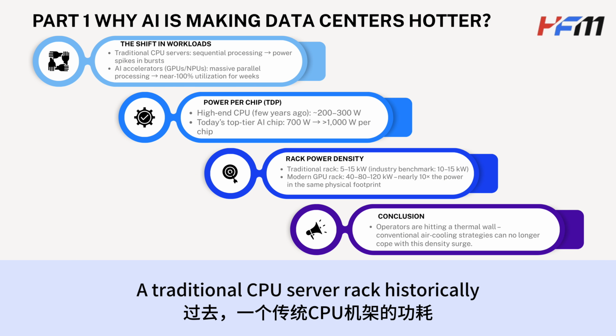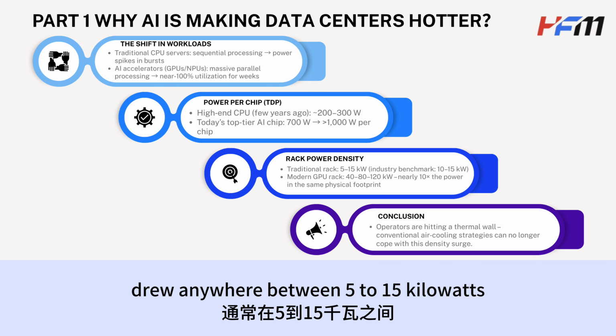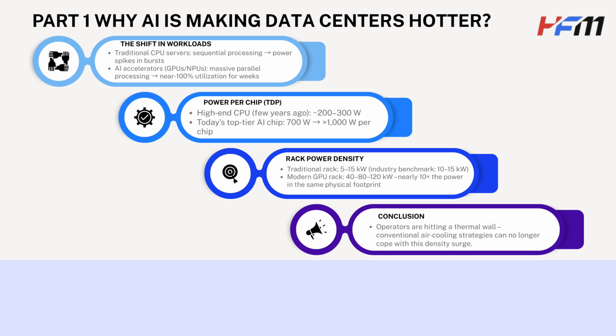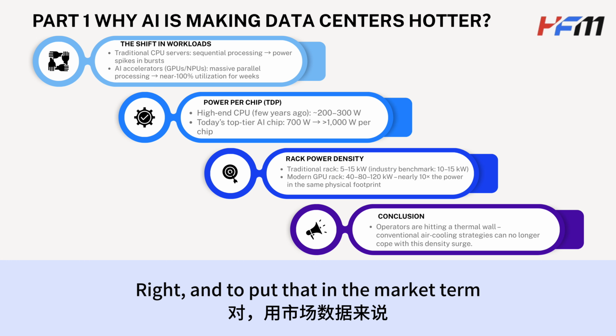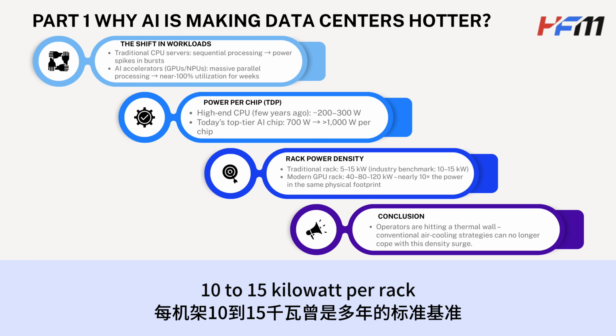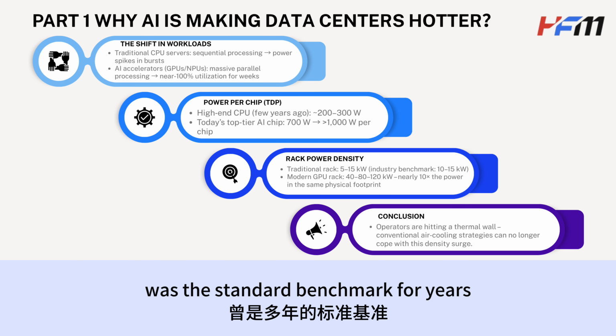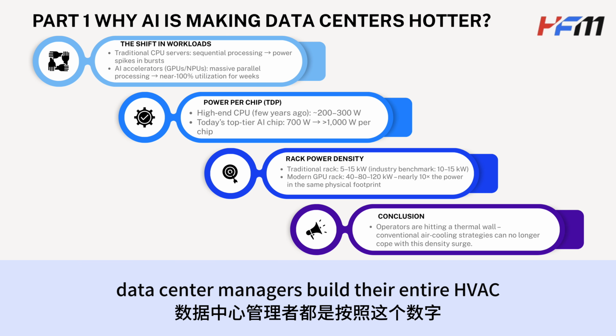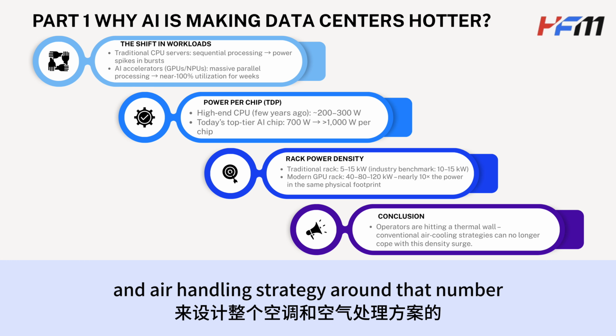A traditional CPU server rack historically drew anywhere between 5 to 15 kilowatts. Right, and to put that in market terms, 10 to 15 kilowatts per rack was the standard benchmark for years. Data center managers built their entire HVAC and air handling strategy around that number.